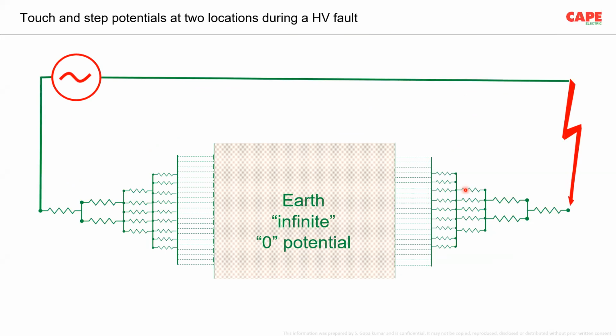Now, this is only an equivalent circuit which I am trying to explain what will happen. You have a source, you have the line which is faulty, and faulty in the sense it is in touch with the earth. And now you have the RE here, which is going to create a voltage gradient at the place of the fault. And near the neutral, because the transformer neutral is also connected, there is another potential, a voltage gradient created.